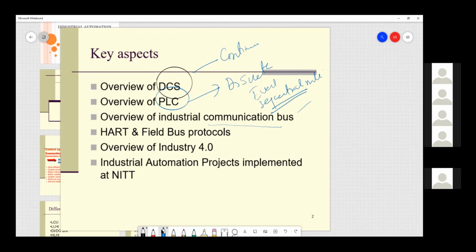The next one we are planning to discuss is communication bus; the very famous one is 4 to 20 milliamps analog communication. Initially there was a 4-wire transmitter, then 3-wire, and nowadays people use a 2-wire with 4 to 20 milliamps. Earlier, even pneumatic transmitters used 3 to 15 psi.